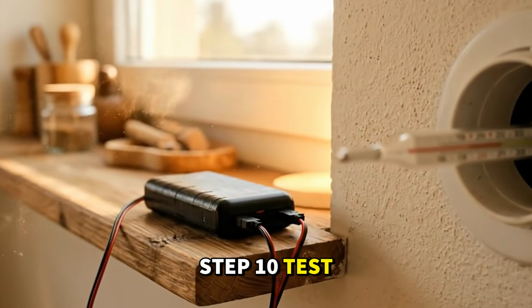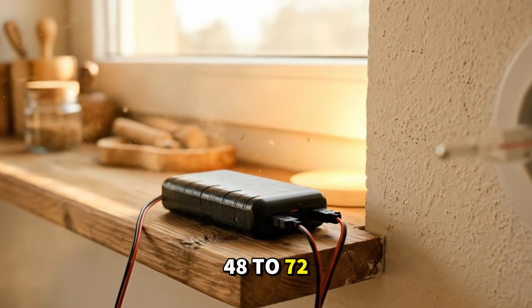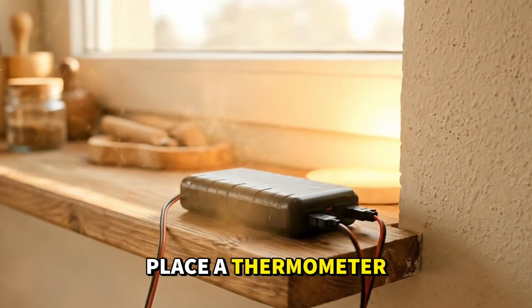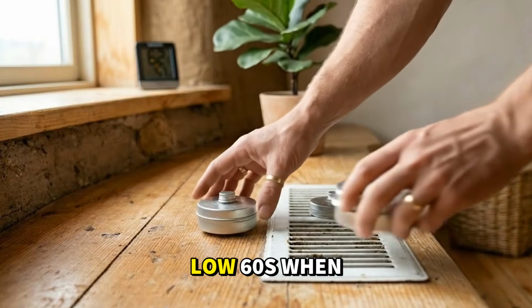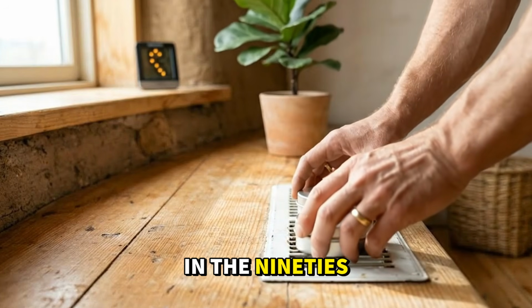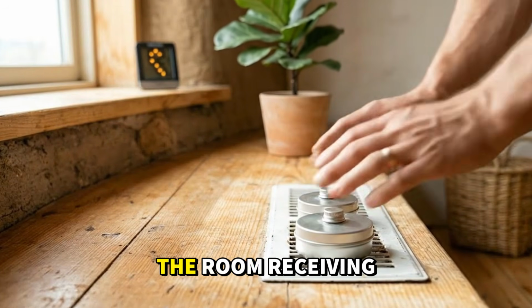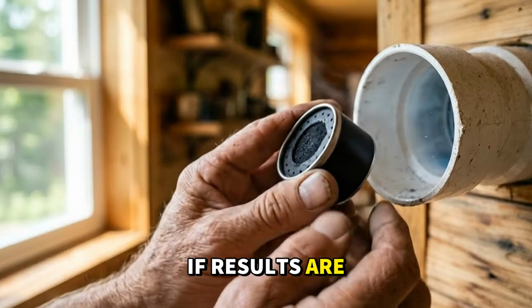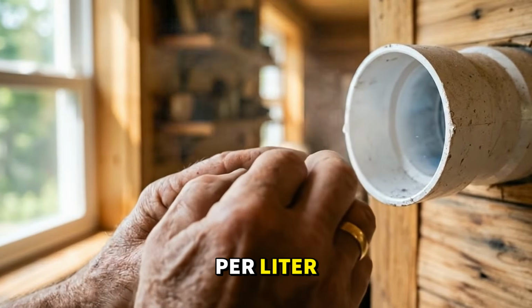Step 10. Test the system. Run it for 48 to 72 hours. Place a thermometer at the outlet. You should read low 60s when ambient air is in the 90s. Deploy a radon test canister in the room receiving the air. If results are below 4 picocuries per liter, you are clear.